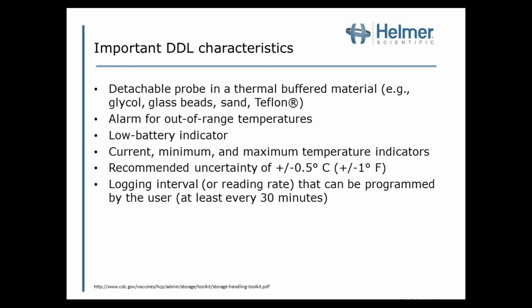Current minimum and maximum temperatures are very, very important because you need to know not only what the temperature is at the time you read it, you need to know what the temperature was since the last time you read it. And the recommended uncertainty is plus or minus 1 degree Fahrenheit, and as I mentioned earlier, at least have a logging rate of every 30 minutes for that continuous read.